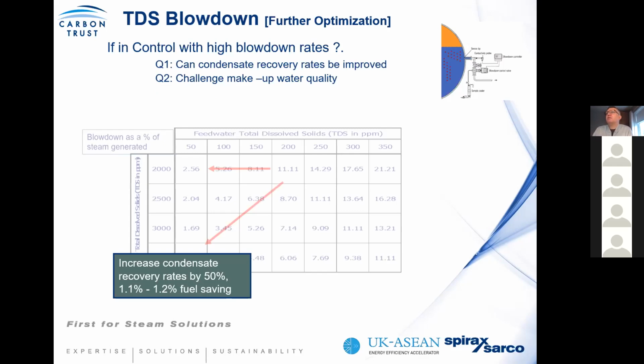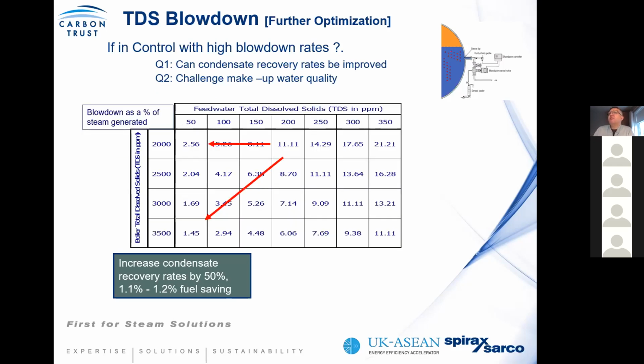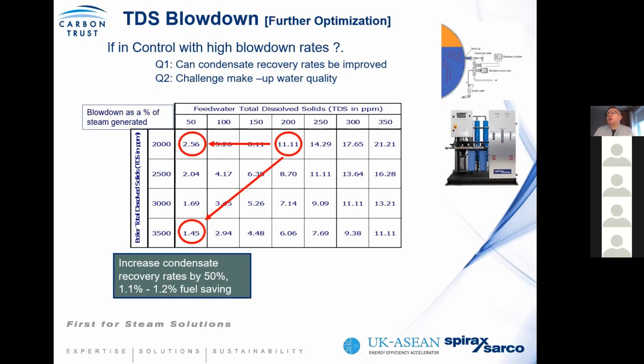So let's consider, for example, that you are operating with, say, 200 ppm in boiler feed water, and you were controlling at 2,000 ppm, because of silica, for example. In this case, your blowdown rate will be over 11%. So in other words, it's quite a lot of water being lost purely because of controlling to upper parameters, which may be determined by silica or alkalinity.